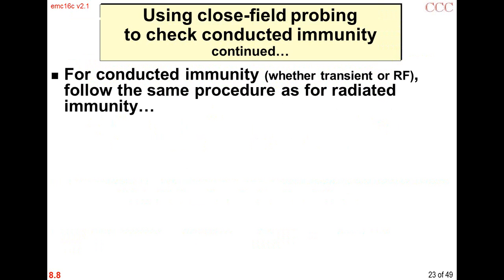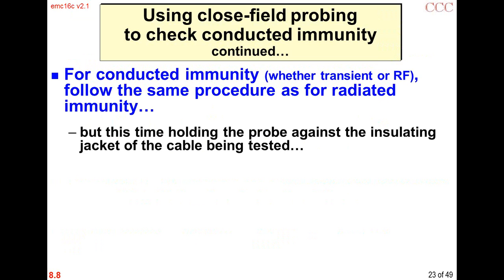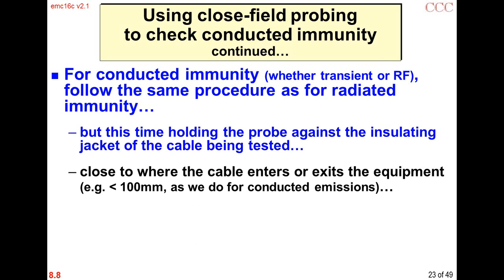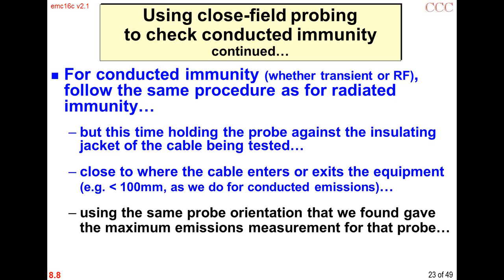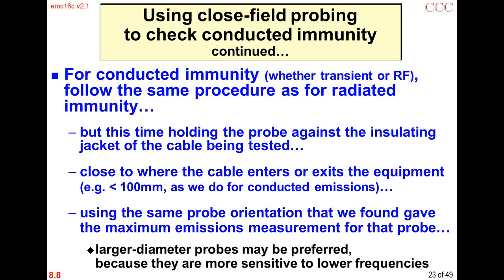For conducted immunity, we follow the same procedure, except that this time, just like for conducted emissions, we hold the probe against the insulating jacket of the cable being tested, close to where the cable enters or exits. We use the same orientation that we found gave the maximum emissions measurement for that probe. And again, we prefer larger diameter probes because they're more sensitive to lower frequencies. Now, quite likely, if we're testing cables, we prefer to use a clip-on probe, like a current clamp.